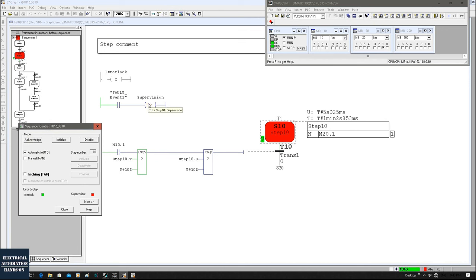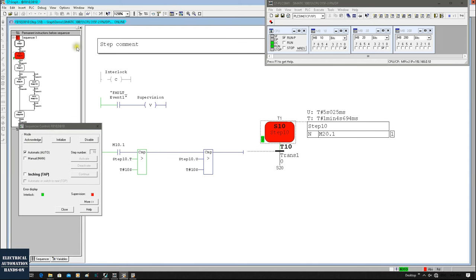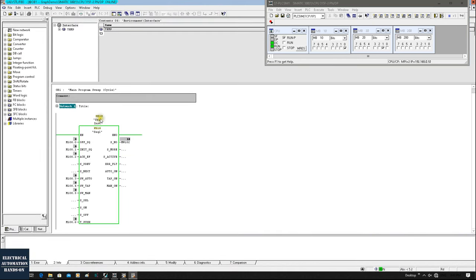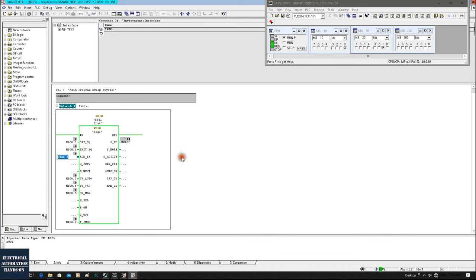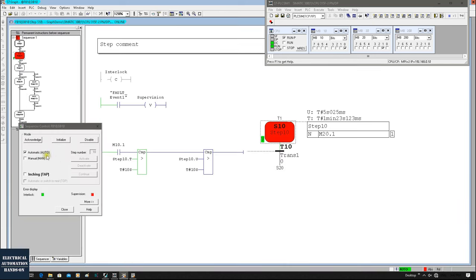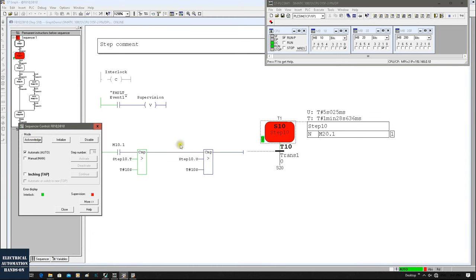However after the supervision clears, the step is still held because it's waiting for us to do a confirmation — an acknowledge. The acknowledgment typically comes from two areas: one is from the control panel where we can click Acknowledge, and another way is via program — by turning on the Acknowledge input on the function block call, using a rising edge from zero to one. Here I'll use the button to acknowledge.